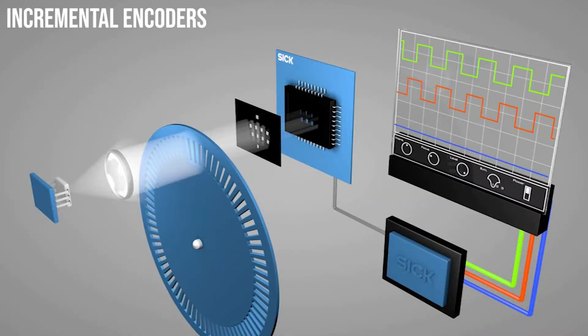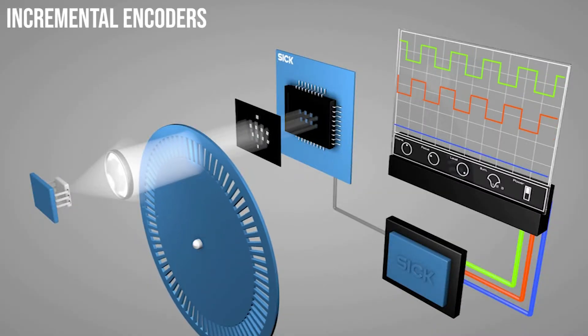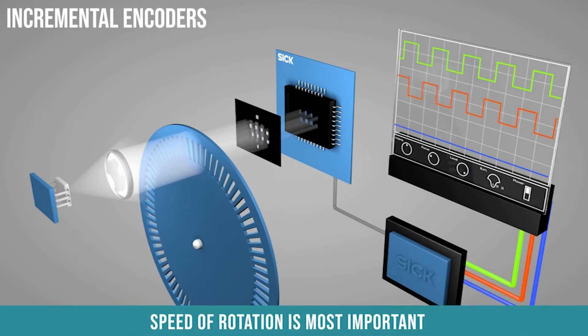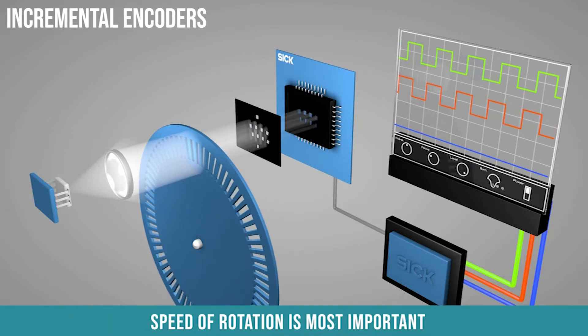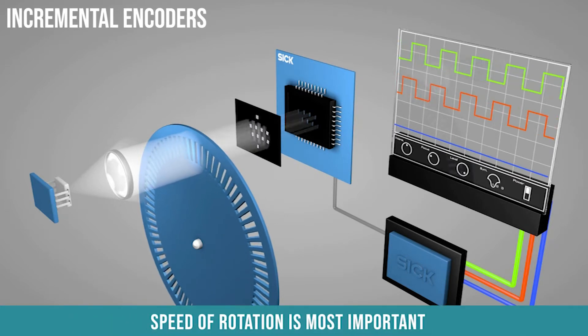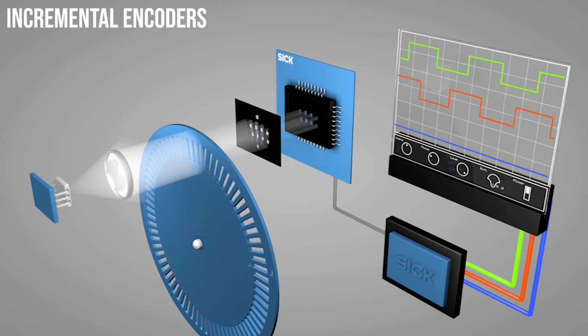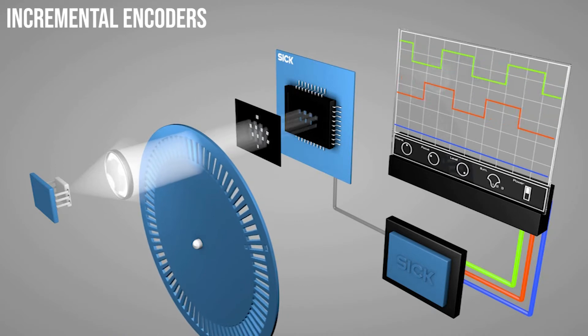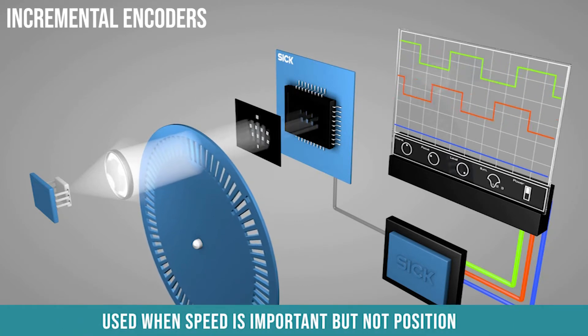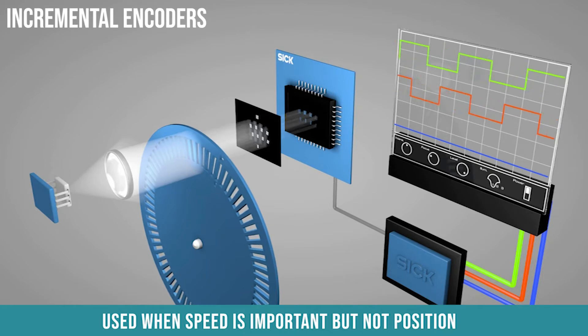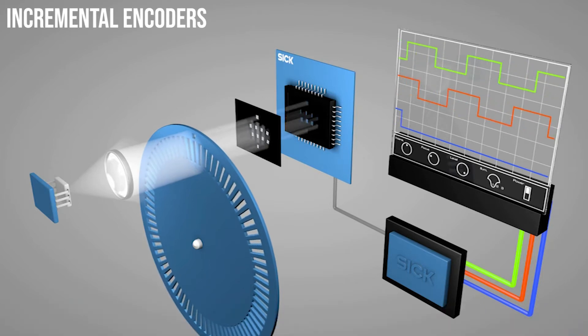Now let's dive into the difference between the two. Incremental encoders are a common type of basic encoder. They're mostly used in applications where the speed of rotation is the most important information you're trying to gather. For example, they are commonly used in pumps, fans, conveyors, and other applications where it's important to know speed but not position.